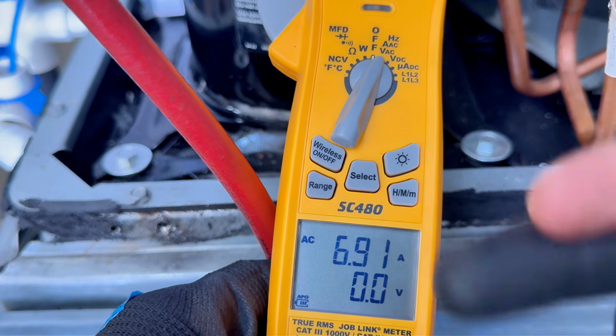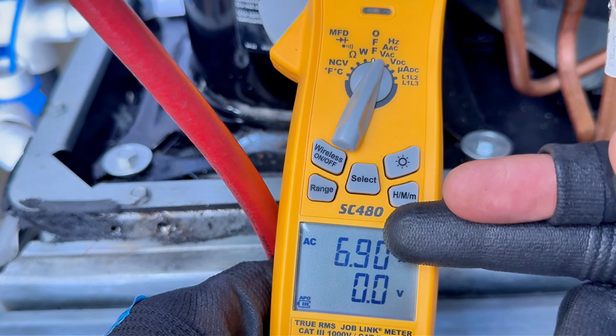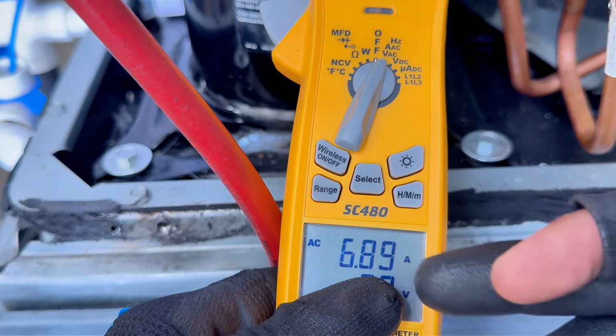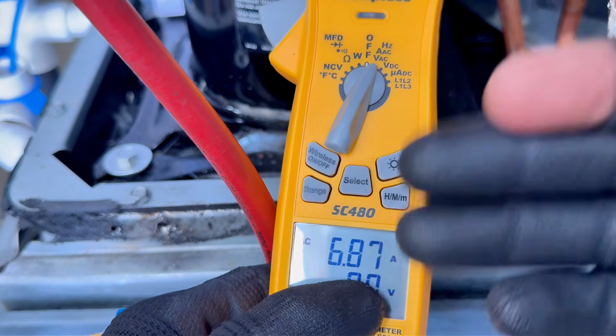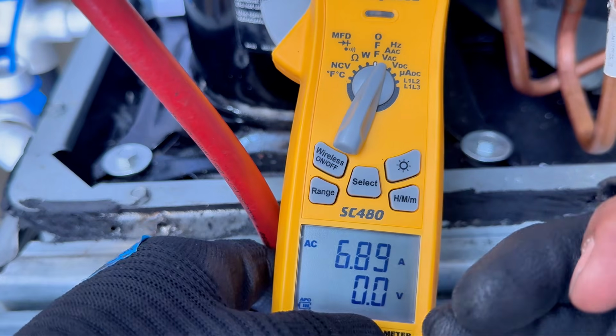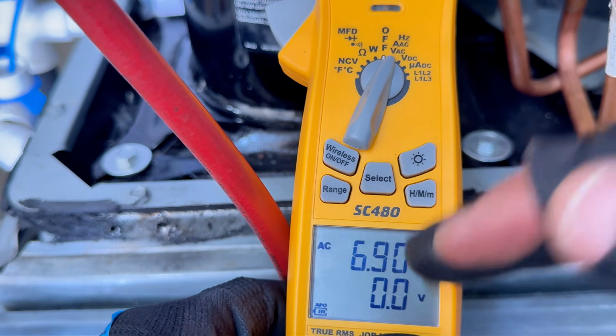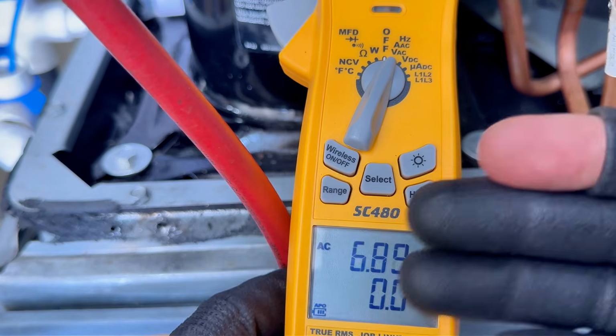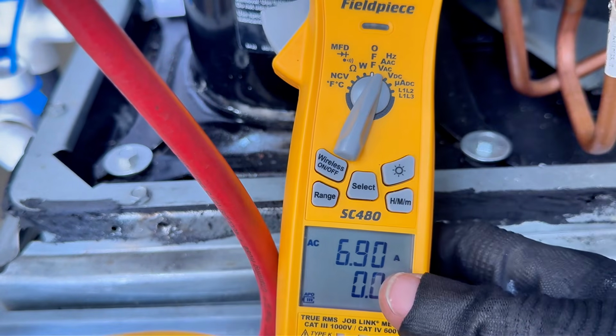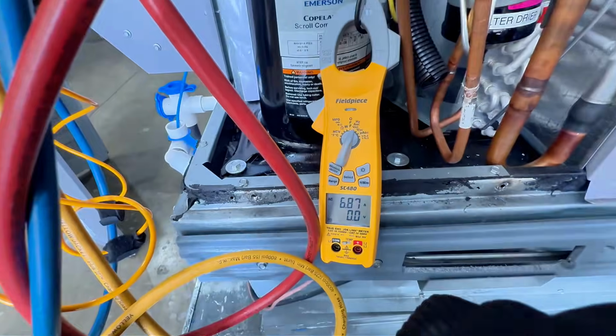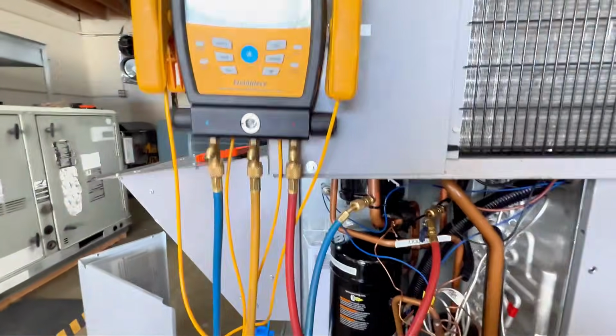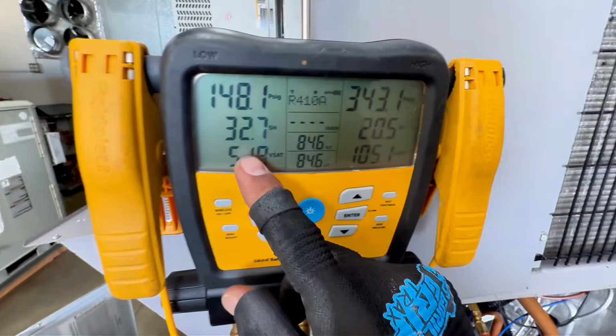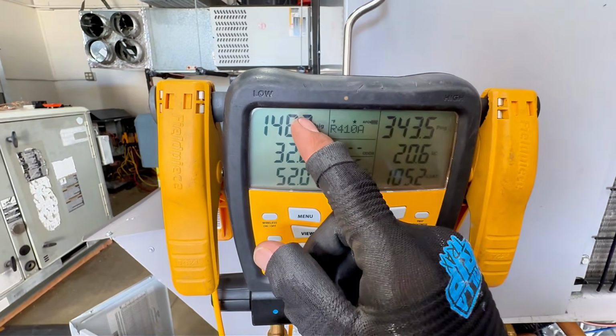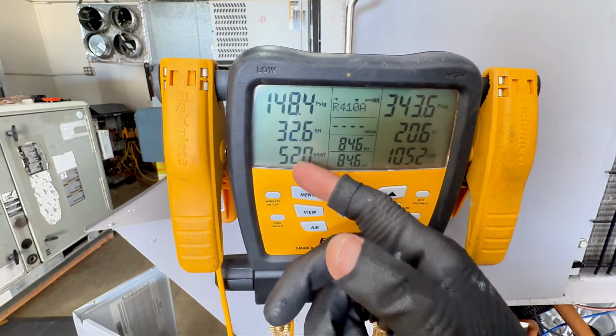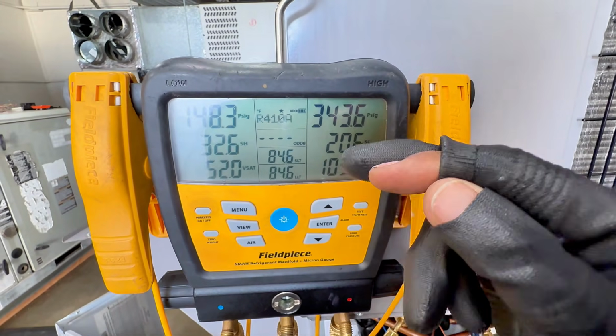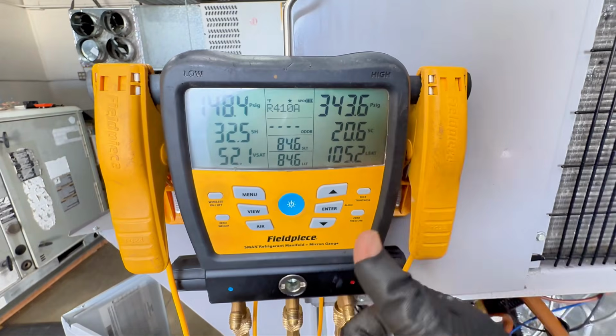But you see, as I'm charging refrigerant, if it's overcharged, then it has more refrigerant to pump. It has more work to do. Your current goes up. Now, this is just a little simple thing to show you. But a lot of the times, you go to a job, especially with a TXV, and you find that your suction pressure is a little bit higher than usual. Your superheat is okay because it has a TXV. Your high side pressure is a little bit high, and your subcool is high.